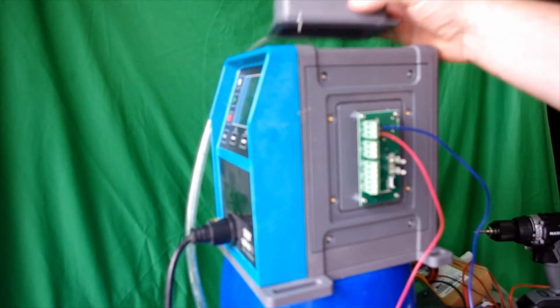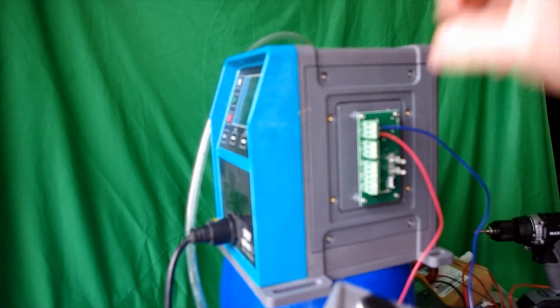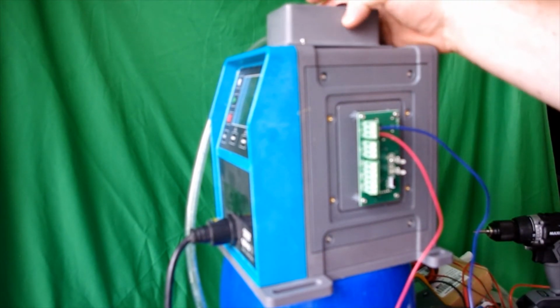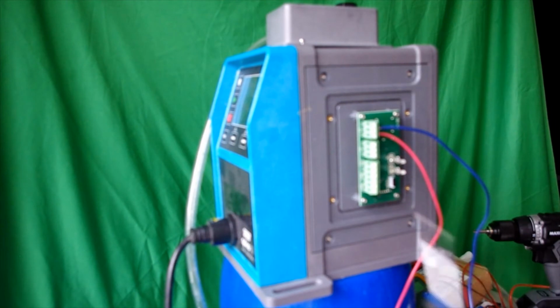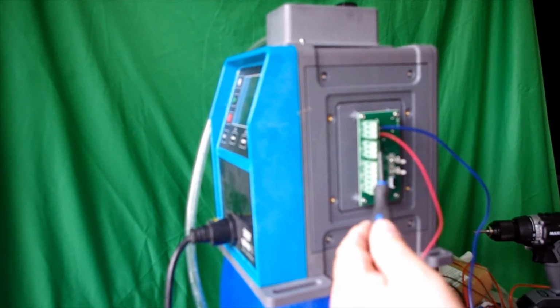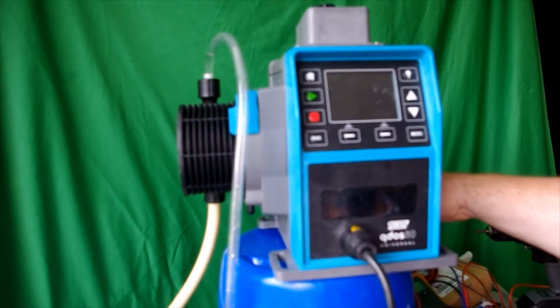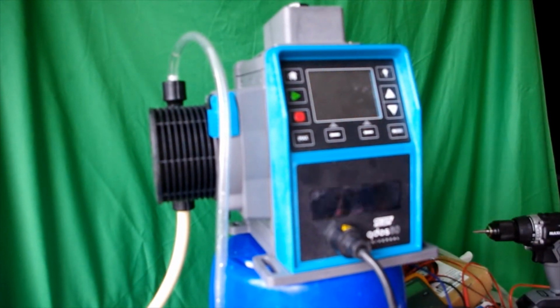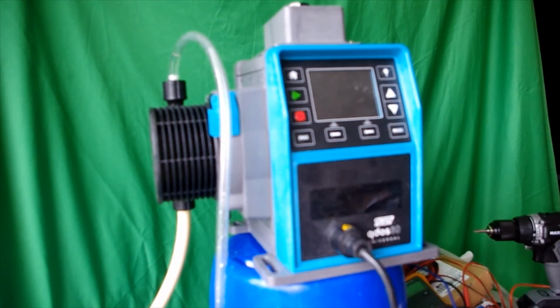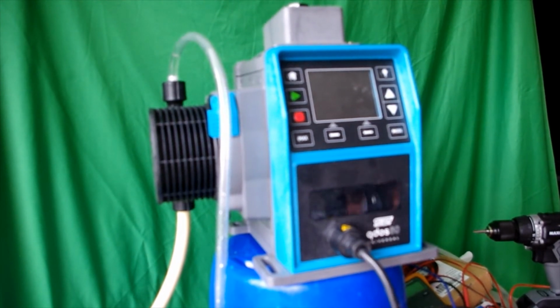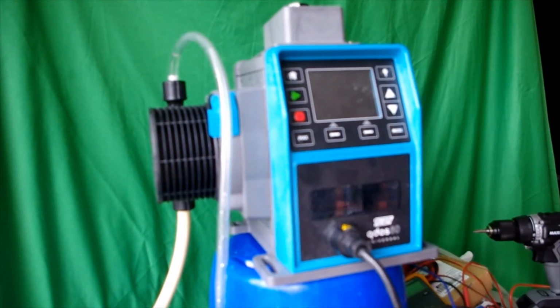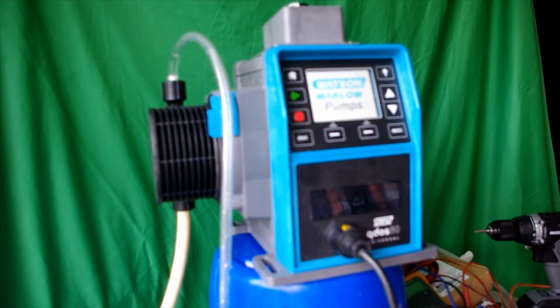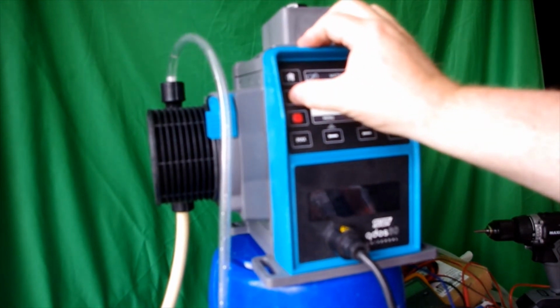Now normally these wires would be wired through your gland connector here and then down through conduit connector into your panel. So as you can see, I've wired up both alarm, ground, and positive, and now that I've wired it all up, I've closed my NEMA 4X module. I plumbed up the conduit connector. Everything's all done. Now I'm ready to turn my mains power on. The pump's up and running. So I could turn the power on now.